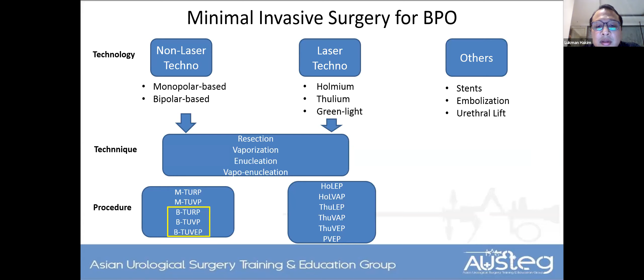The procedure, we may also use the monopolar for resection, monopolar for vaporization, although not ideal. But on the other hand, we also can use bipolar for resection, vaporization, and vapo-enucleation. And also in the field of laser, we can use it for either enucleation, vaporization, or a combination of both. Now, what we need basically for enucleation, resection, or vaporization is first the electrocoagulation device. Here we can use a monopolar or bipolar, which of course have different specifications.